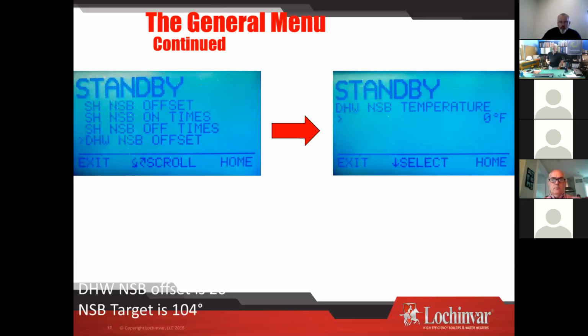Now this one here, this is a more common feature that you're going to use. This is your night setback temperature. So with this one here, I can tell my boiler not to make domestic hot water at night. So what I do is, about 9:30 at night, my boiler will lower the targeted temperature in my tank. So it drops it down from 124 down to 104 degrees.